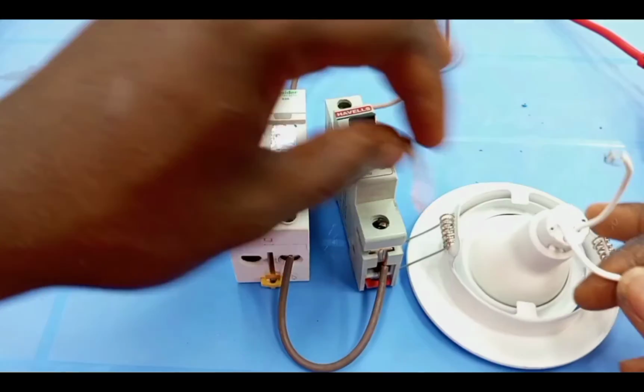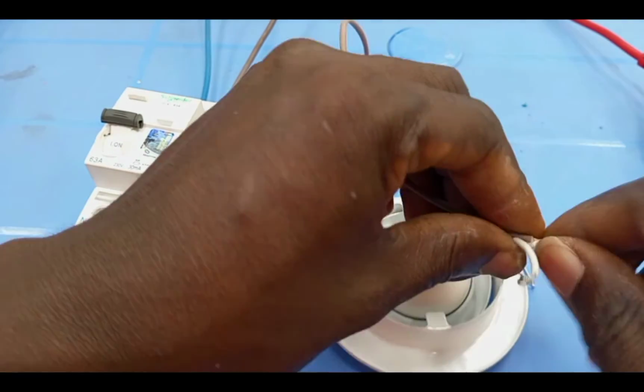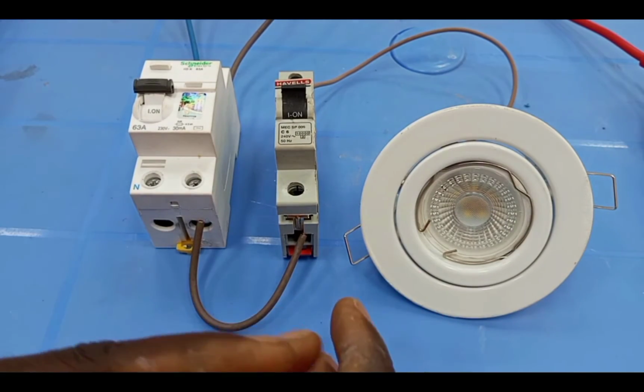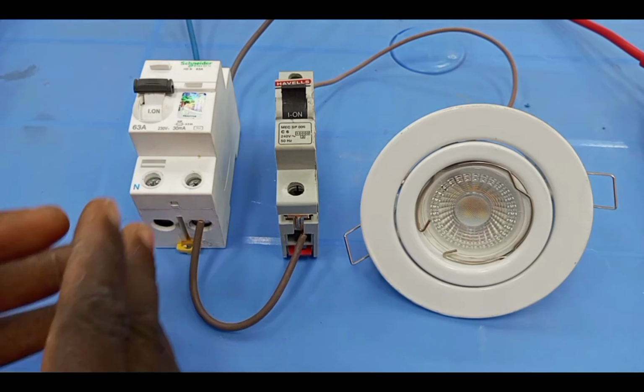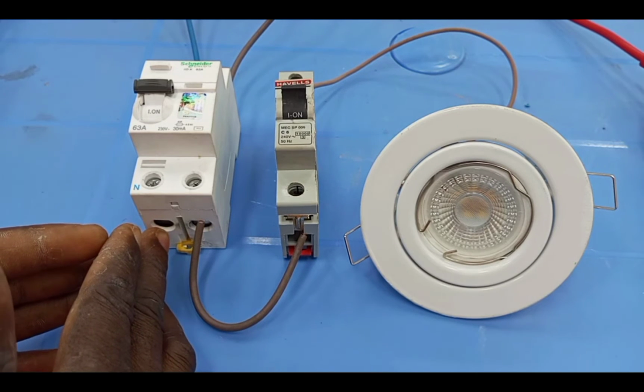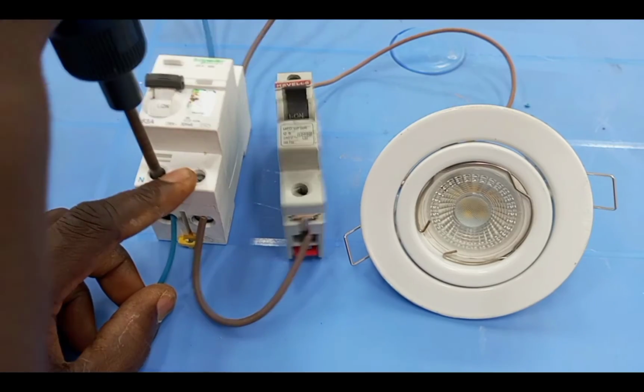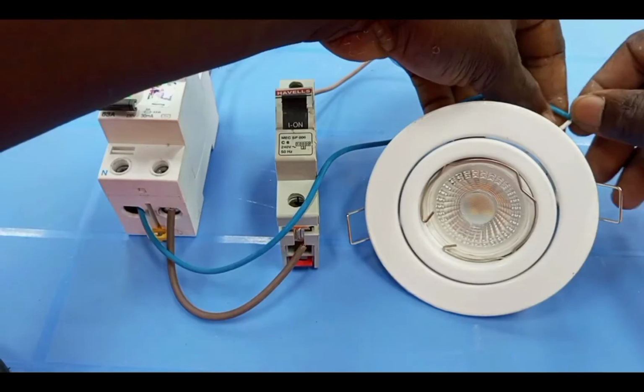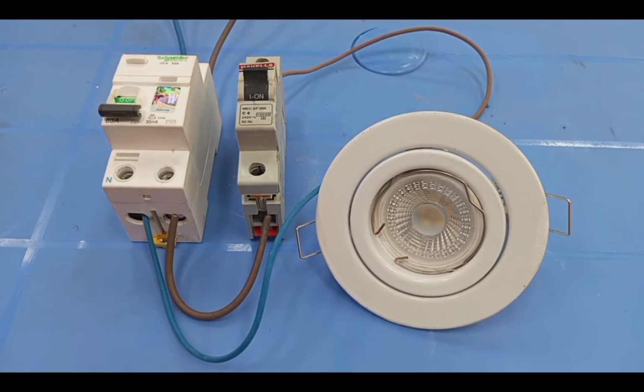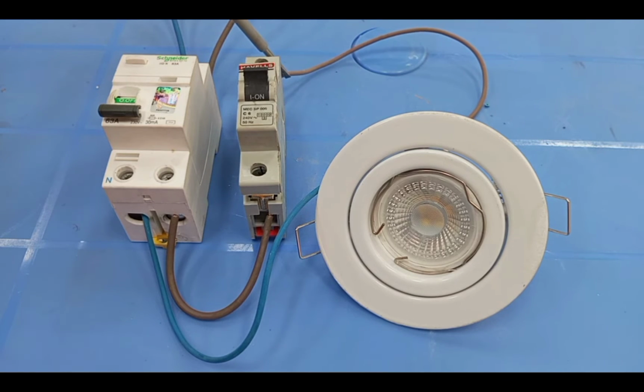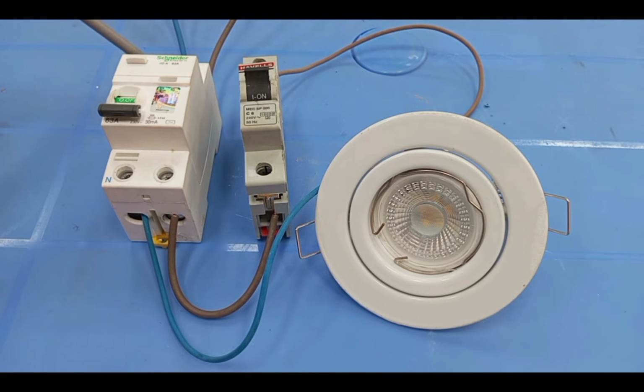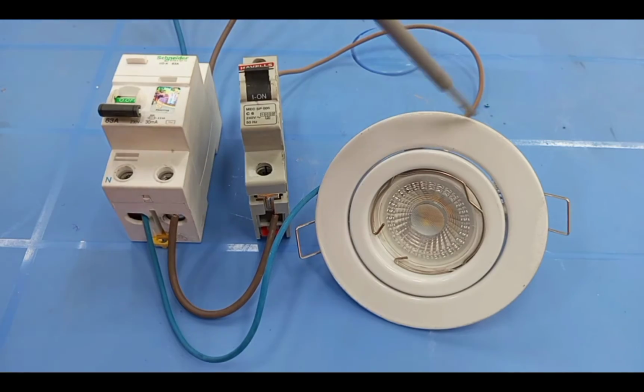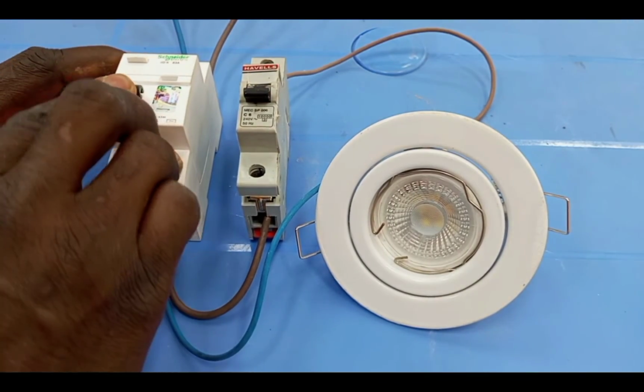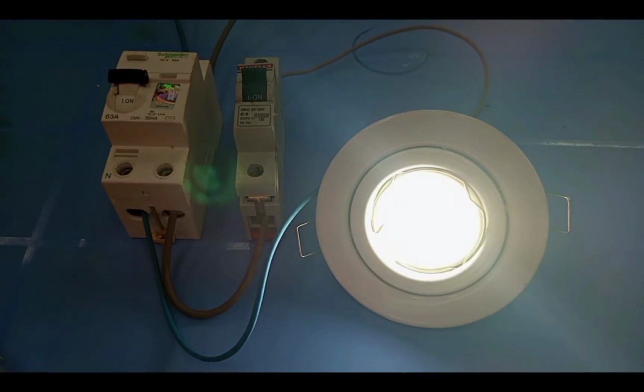Okay, so this is my live output from the miniature circuit breaker, and I will connect it to the lamp. Then this lamp will need live and neutral to work. And because I am using the RCCB, the neutral must be taken from the neutral terminal of the RCCB. Okay, so this is my neutral to the load. All right, so live input to RCD, live output from RCD to miniature circuit breaker, live output from miniature circuit breaker to load. Then neutral input to RCD, neutral output from RCD to load. Okay, so now if this RCD is on and this breaker is on, the light comes on.